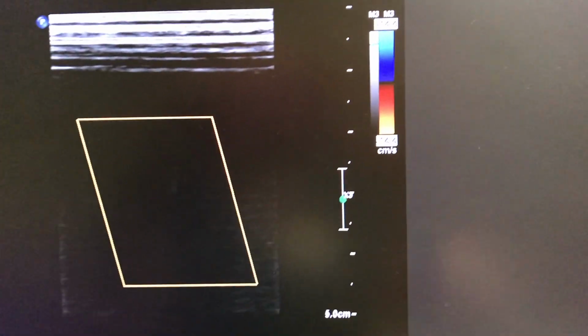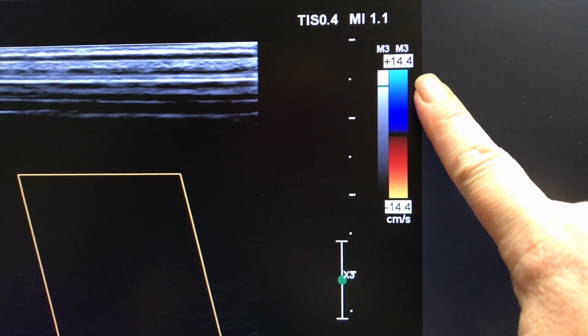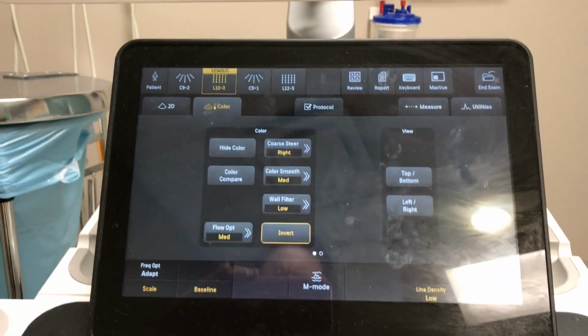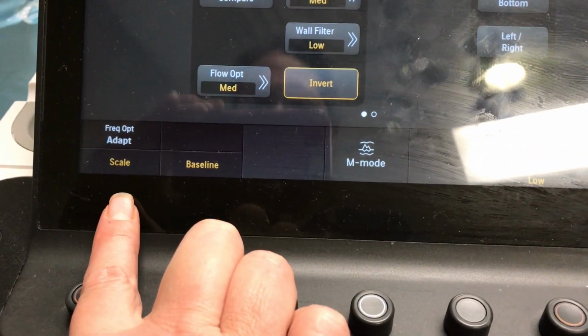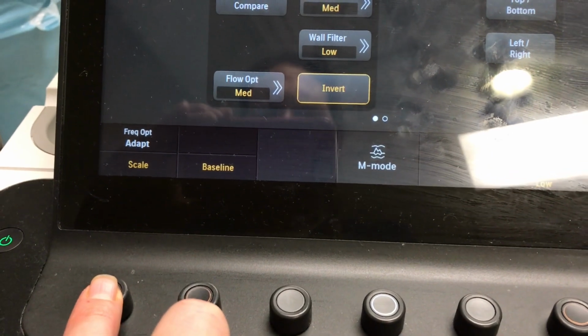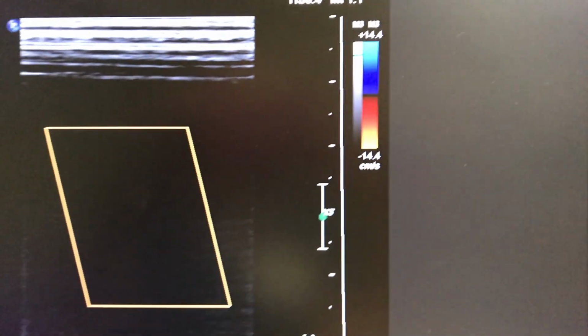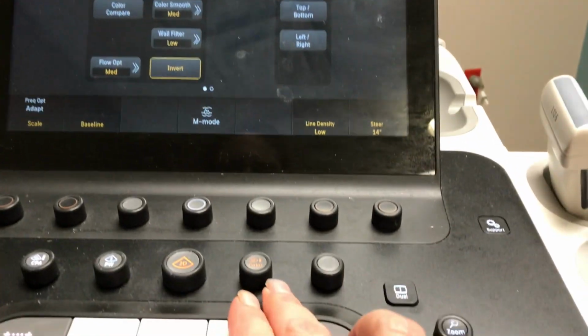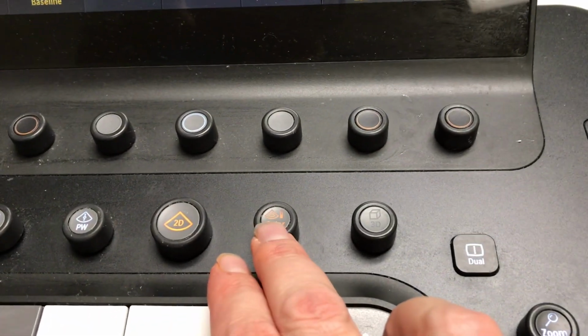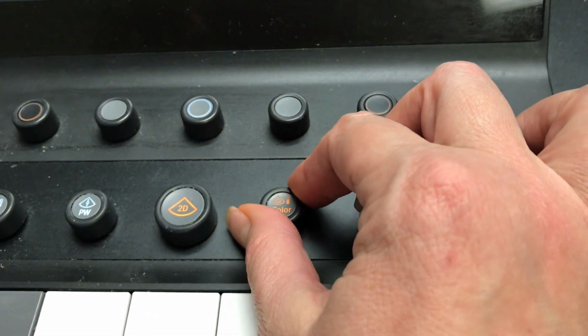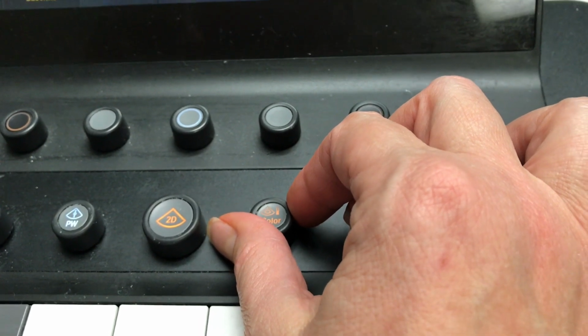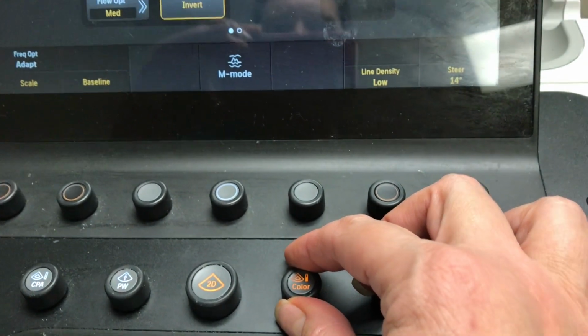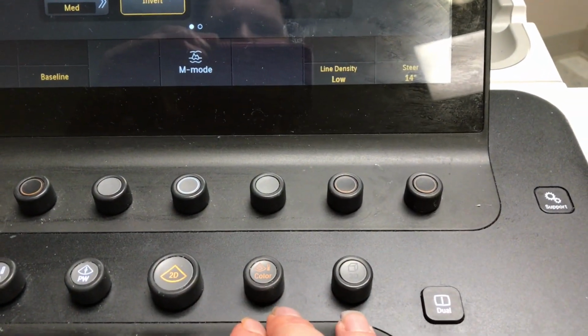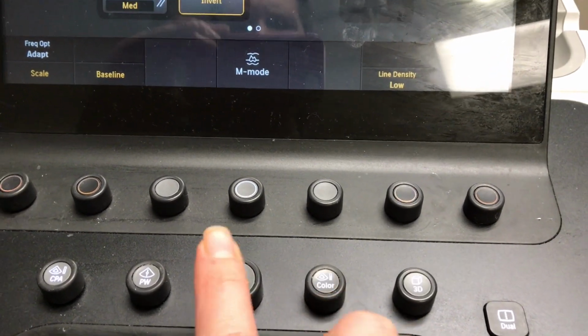If you wanted to change the scale, which you can see the scale up here, again, you come down to the touch screen and see that the scale is highlighted here, so this knob controls it. And you simply turn it to change the scale lower or higher. Once that is set, you can further tweak it by turning the color button that you press to turn the color on. You simply turn it for color gain or to decrease the color gain. And to get the color off the screen and return to grayscale, you select 2D.